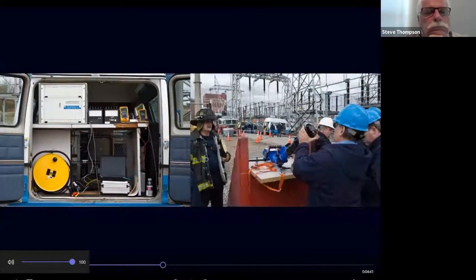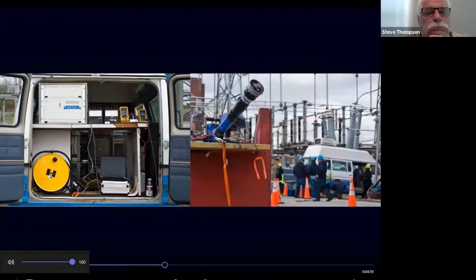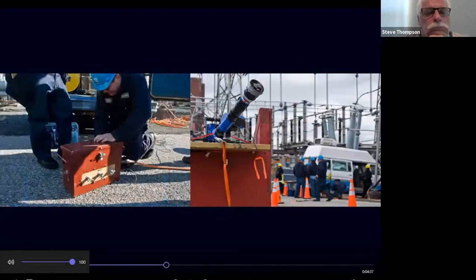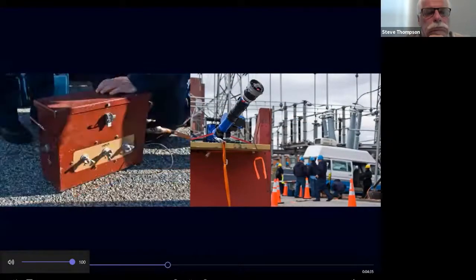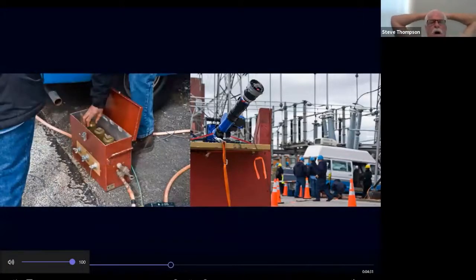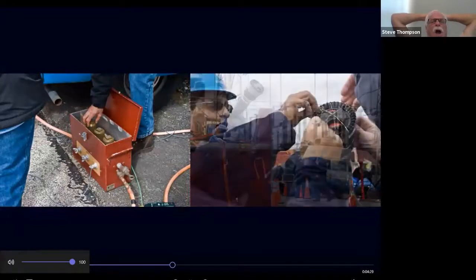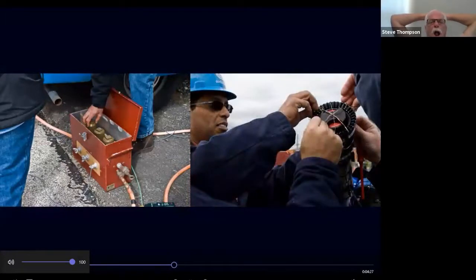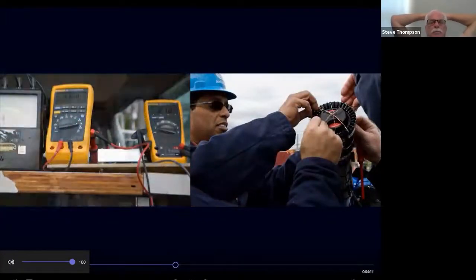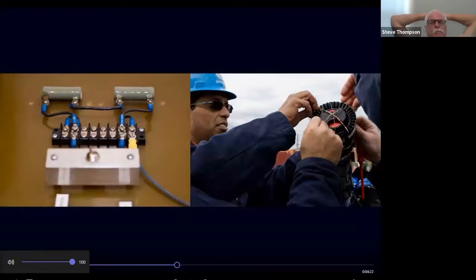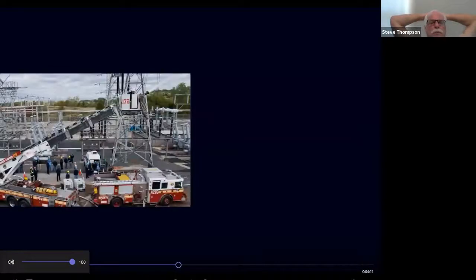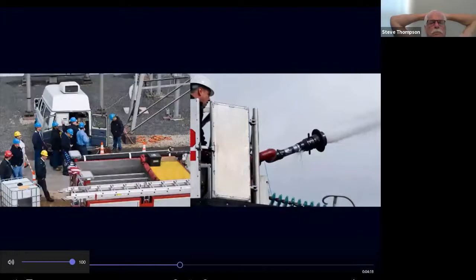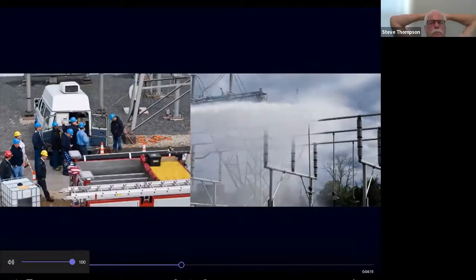What we ended up doing was we set up a portable van at the substation, regrounded it, and then stretched wire to the nozzles. We also installed a safety gap, which is very important in limiting any voltage coming back to the equipment, preventing any damage or potential safety hazards. The wire that was connected to the nozzles was run back to a 5,000 ohm resistor, which simulates someone holding that nozzle. We were able to measure current coming back from the F500 concentrate and water mixture.